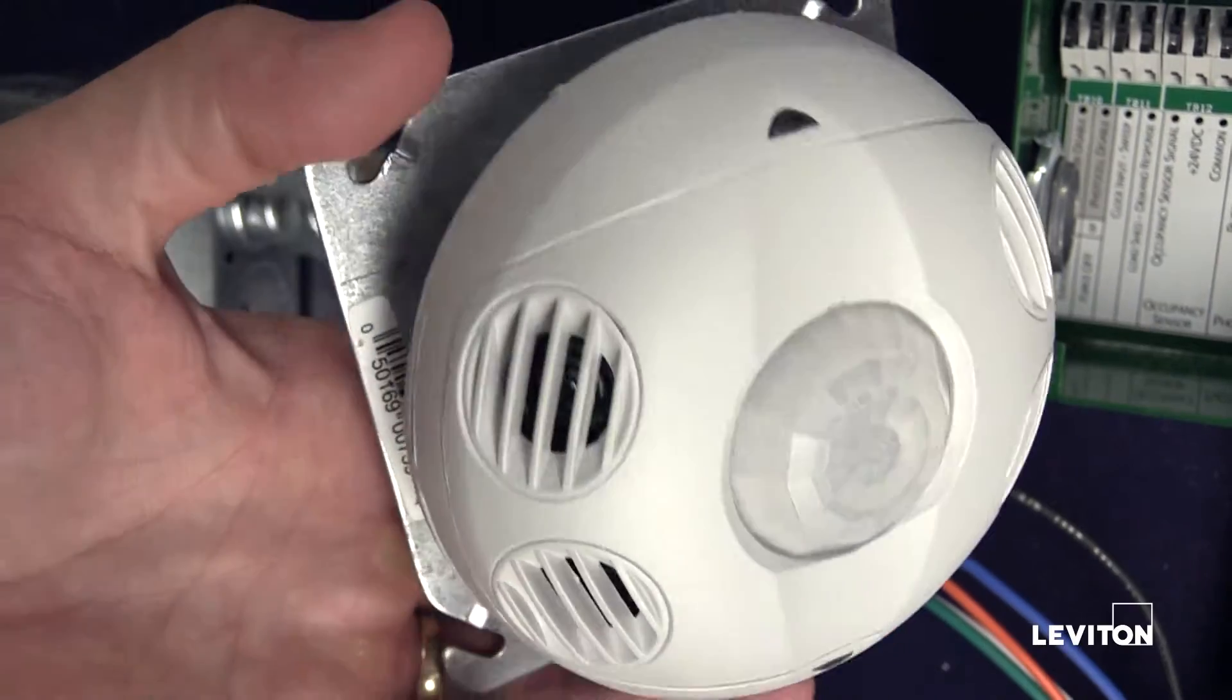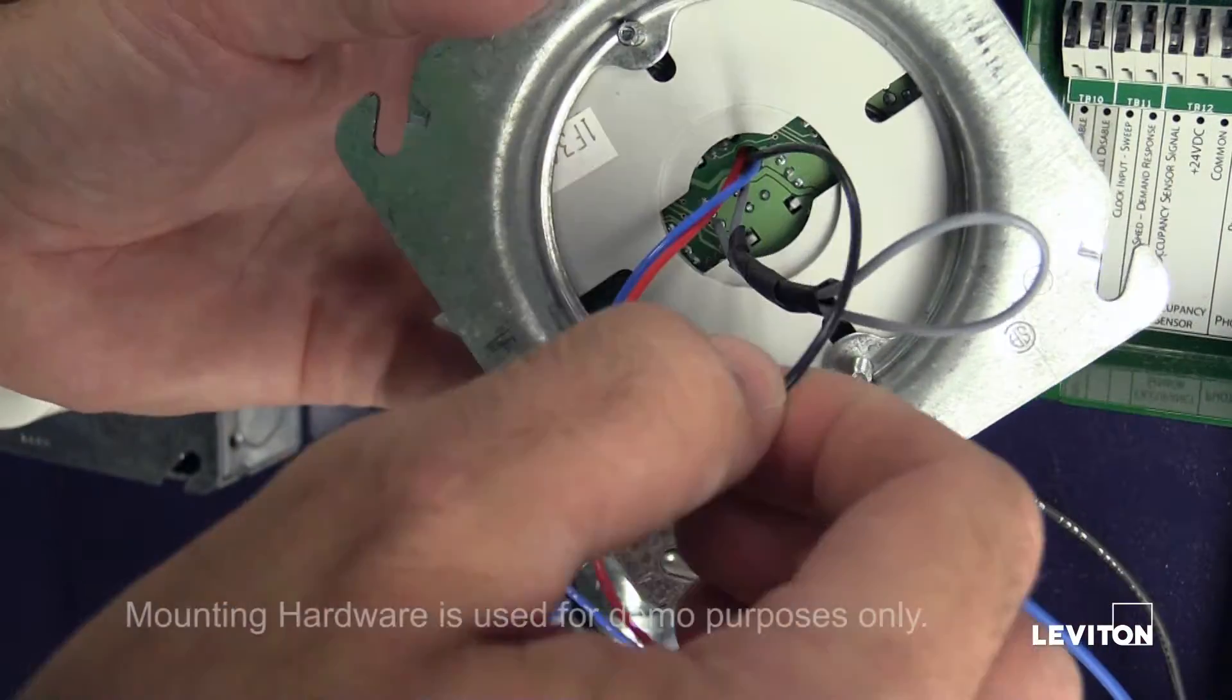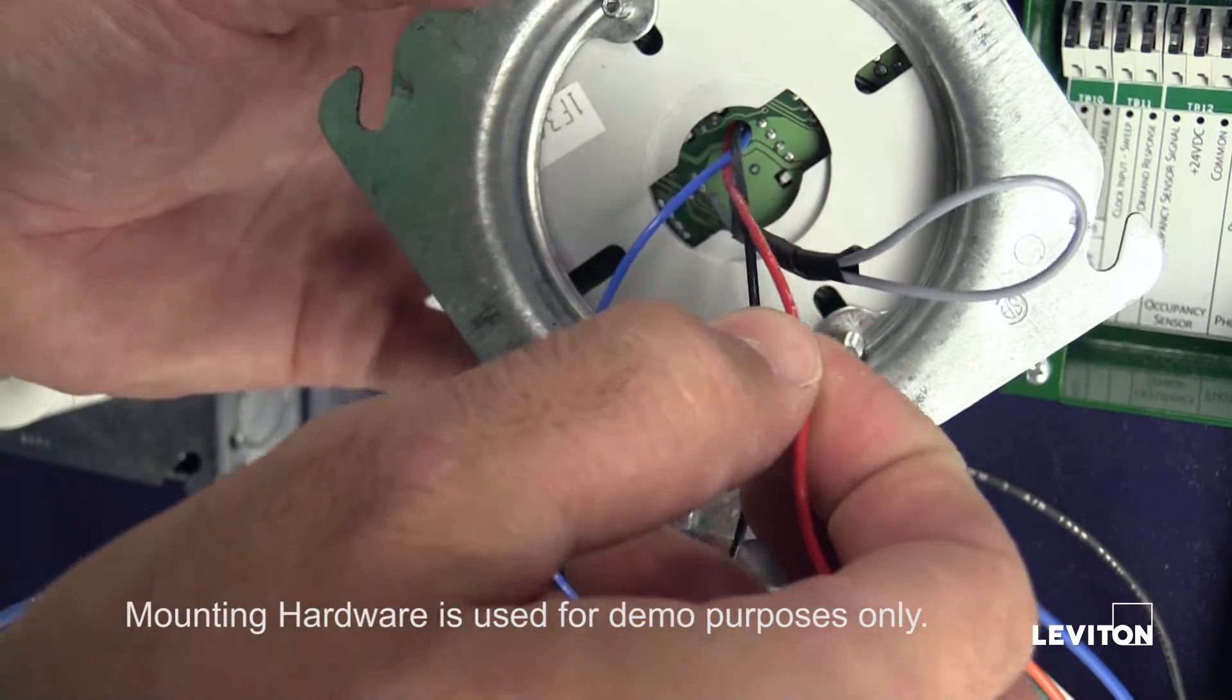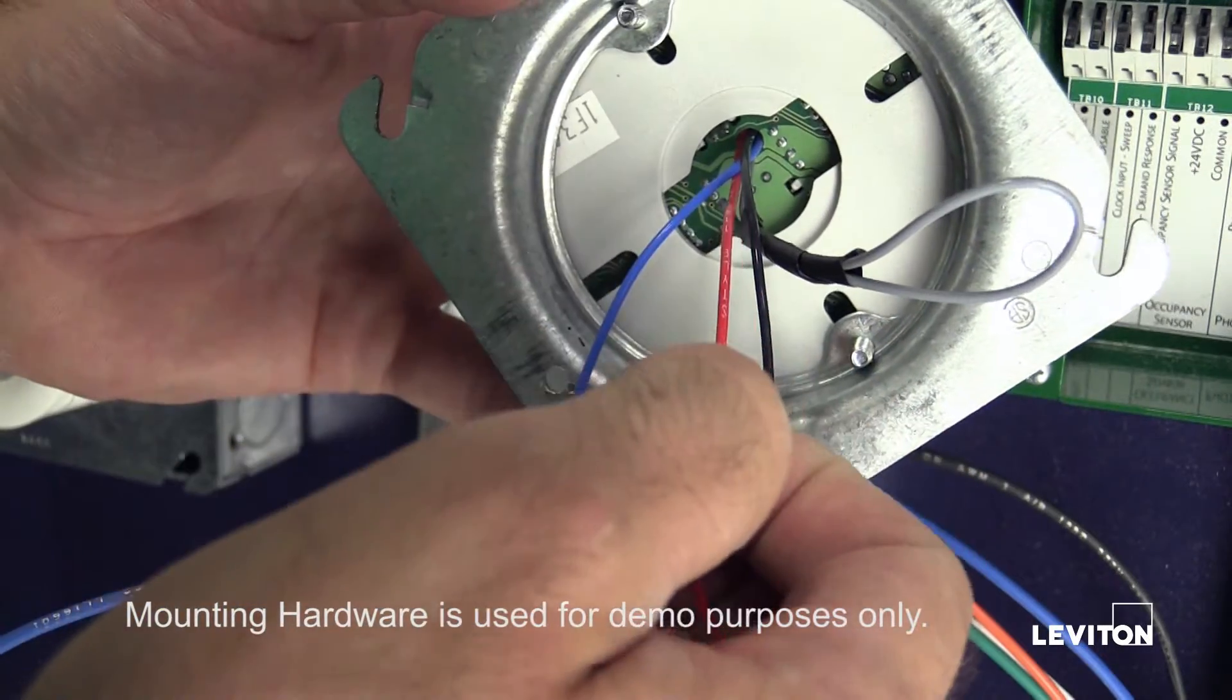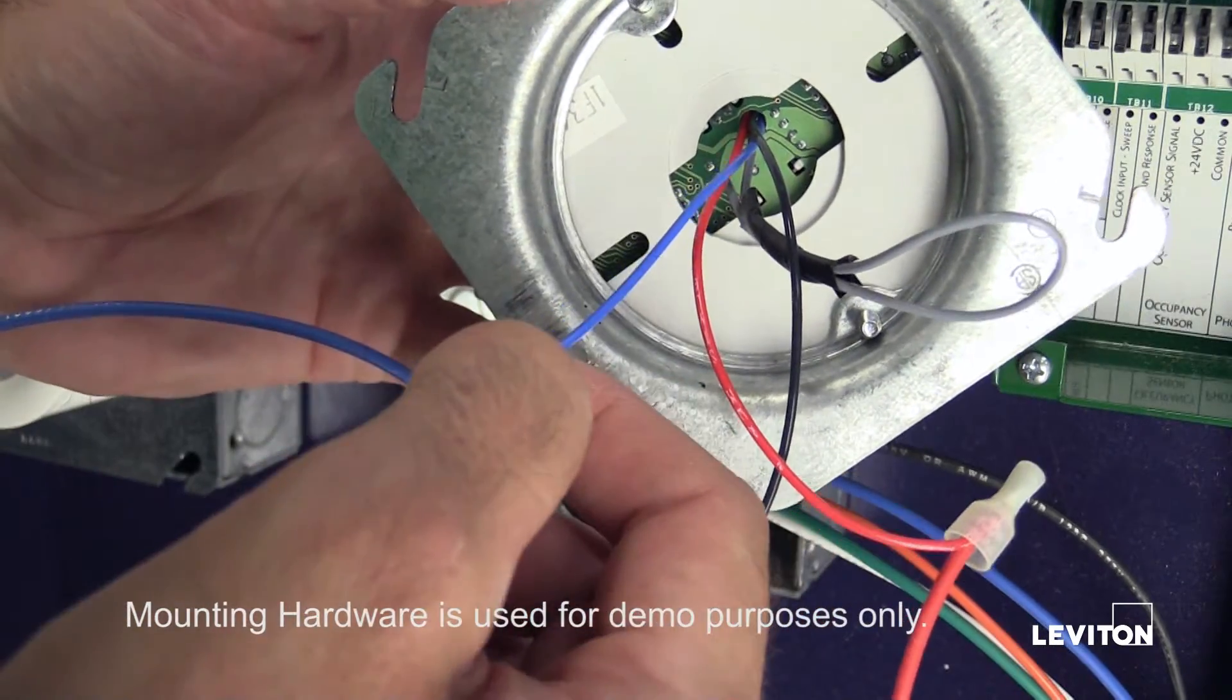This is the Leviton OSC20-M0W Occupancy Sensor. The black wire is your common. The red wire is your plus 24V DC. The blue wire is your occupancy sensor signal wire.